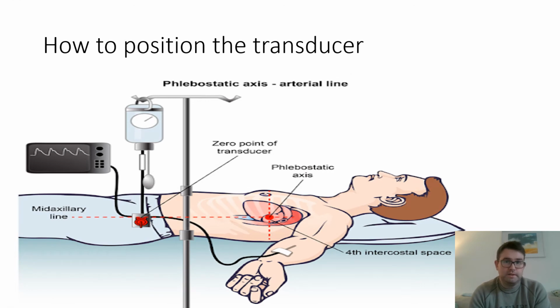It's important to consider where we position the transducer, because this will greatly affect the blood pressure reading that is given. If the transducer is below the level of the heart, you can get an artificially high blood pressure reading on the screen, whereas if you lift the pressure transducer above the level of the heart, you'll get an artificially low pressure on the screen.